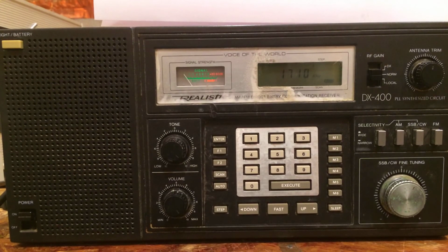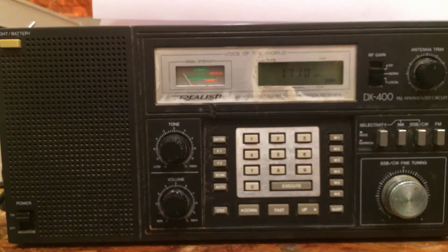So the upshot of all that is that we tuned clear across the AM broadcast band, and we found broadband noise everywhere, hence the name broadband. What this leads up to is that when your predominant sources of RFI were in fact broadband, it was sufficient to tune to a couple, three frequencies per band to gauge whether or not there was a problem in that band. If there was a problem, because it was splattering all over, checking a couple, three frequencies would suffice to find it. And if you checked those frequencies and there was nothing there, it was a real good indication that the entire band was clean.